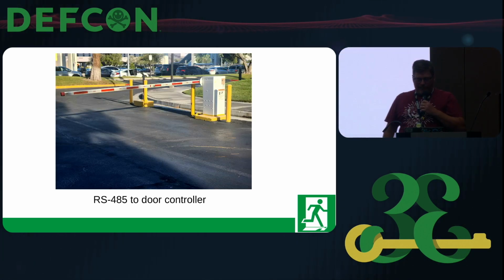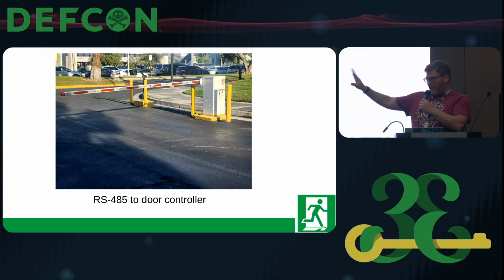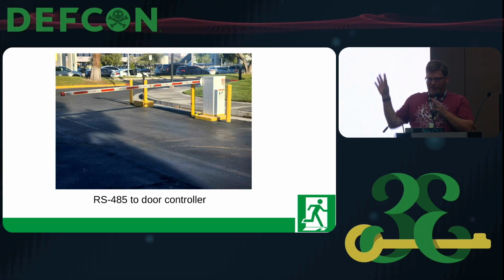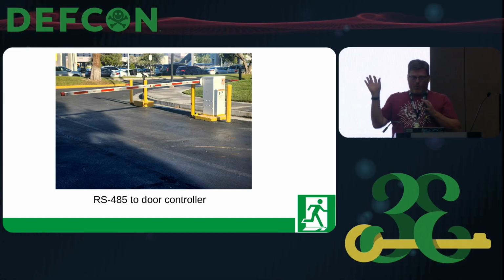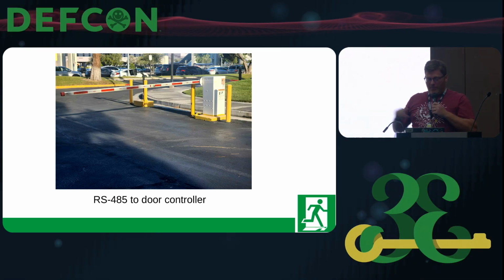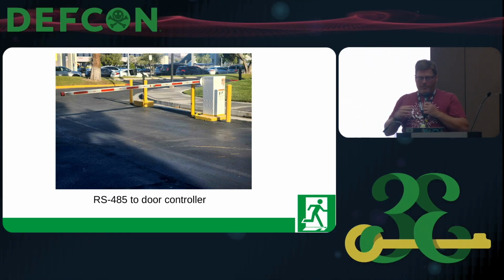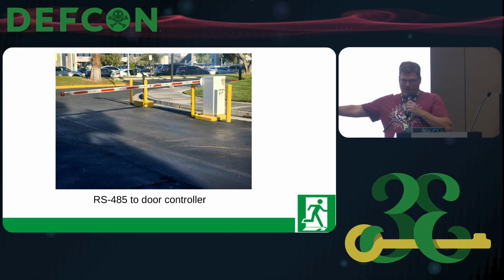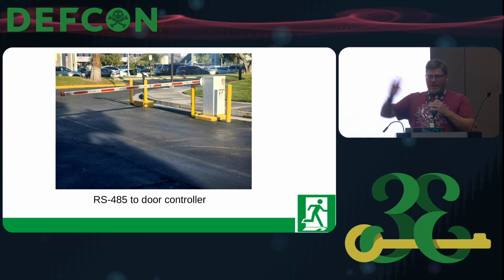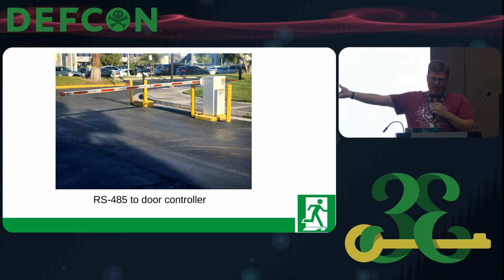Then you have the gateway at the far end of the parking lot, with everything in your building nicely clustered, one or two clusters per floor, but you've got that gate out there with the card reader. Your best bet is probably RS-485 for that, unless you've got a guard shack that has Ethernet, then maybe you do a panel.